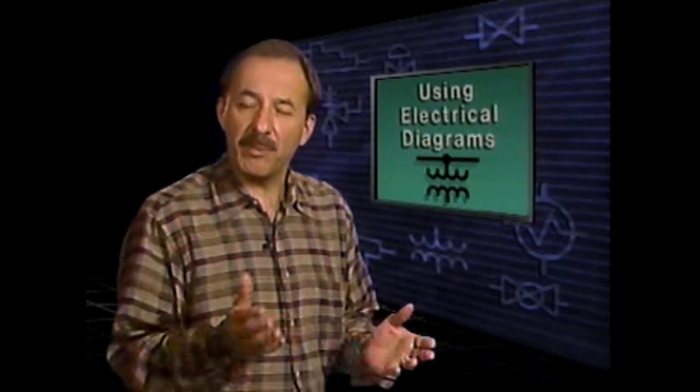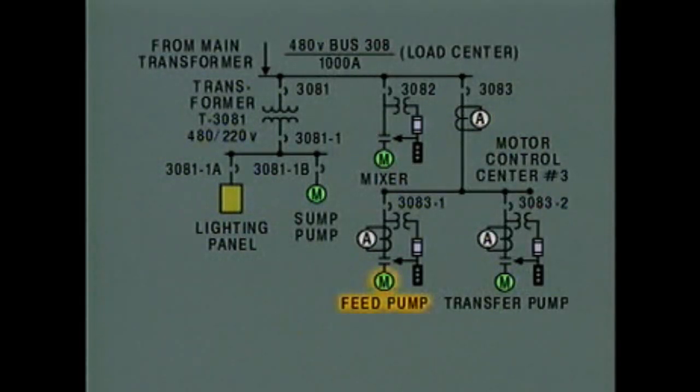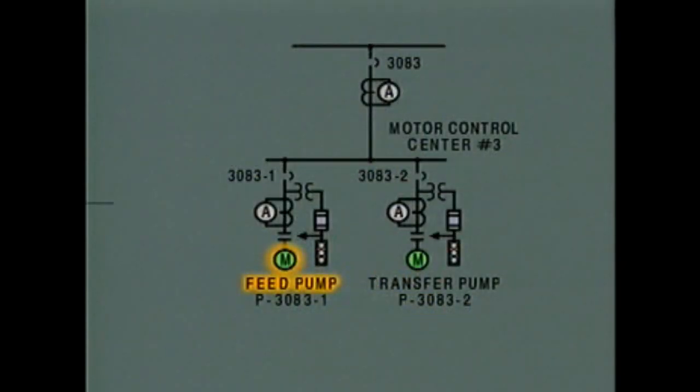Before many kinds of maintenance can be done on plant equipment, the equipment must be isolated. For electrical equipment, this means separating the equipment from the supply of electrical power. To get an idea of how electrical diagrams can help when you need to isolate equipment, let's look at an example. In this example, the feed pump motor has to be shut down for repairs while the rest of the system remains in service. On the diagram, we can see that the feed pump motor is fed by motor control center number three.